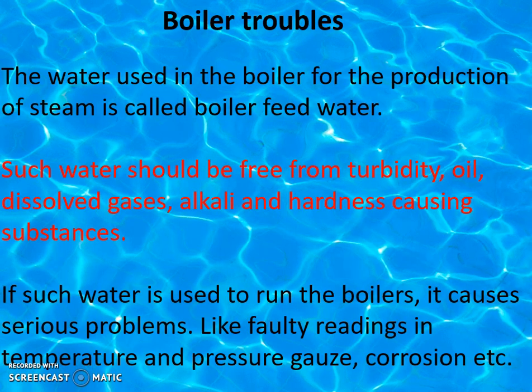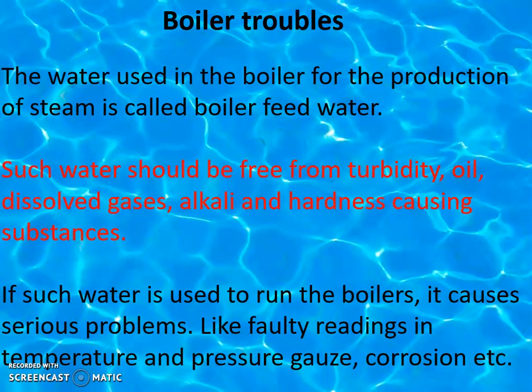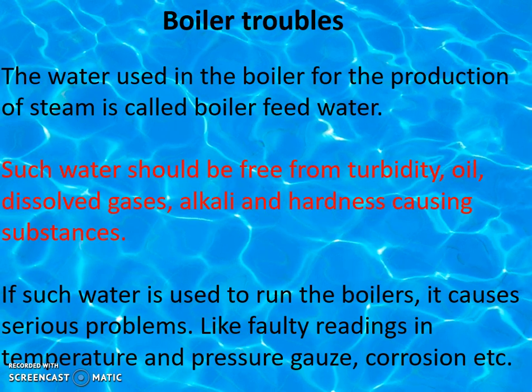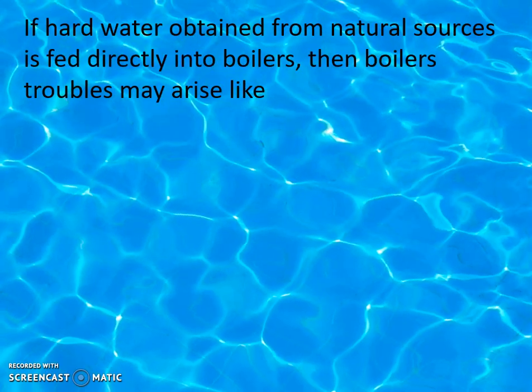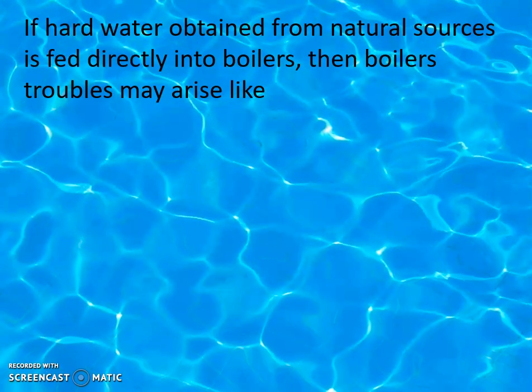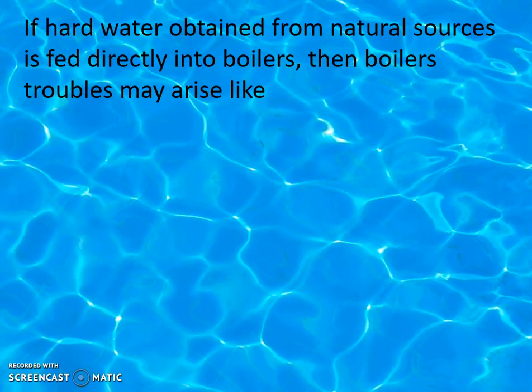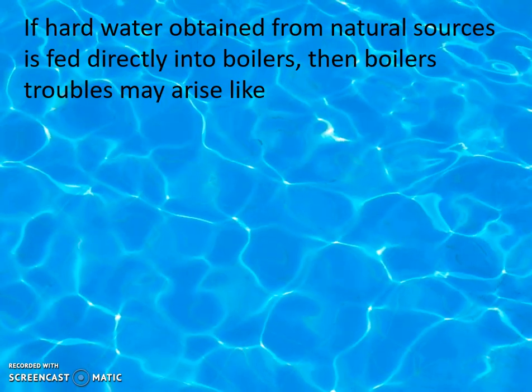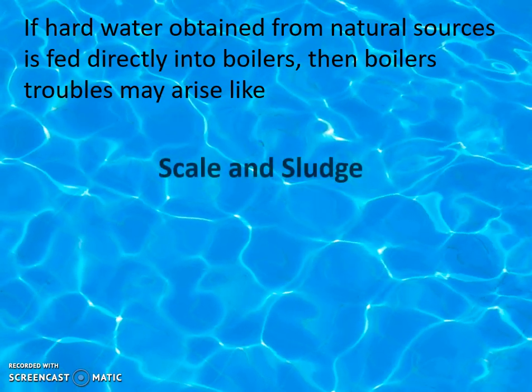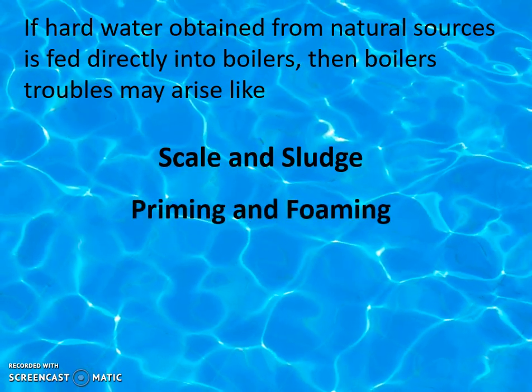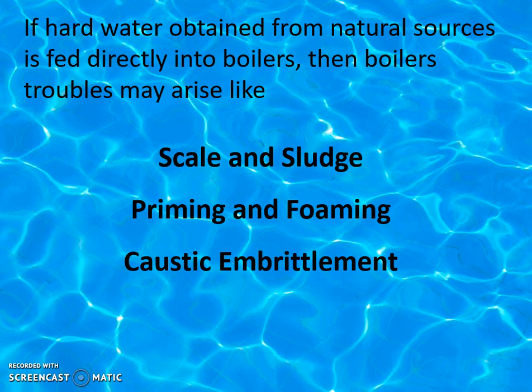If such impure water is used to run boilers, it causes serious problems like faulty readings in temperature and pressure gauges, and is also responsible for corrosion. If hard water obtained from natural resources is fed directly into boilers, different types of serious troubles may arise, such as scale and sludge formation, priming and foaming, and the important one — caustic embrittlement. We will see these one by one in detail.